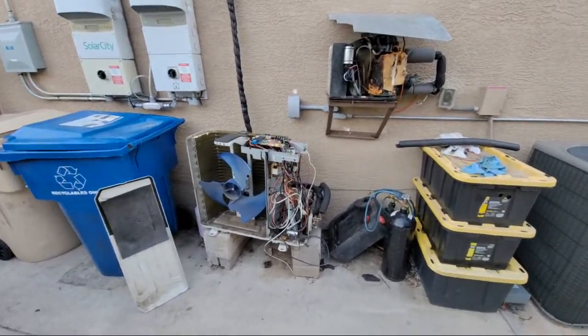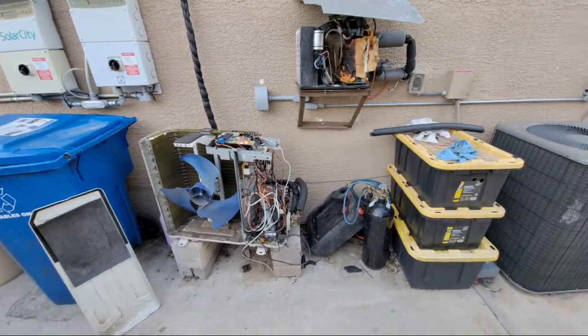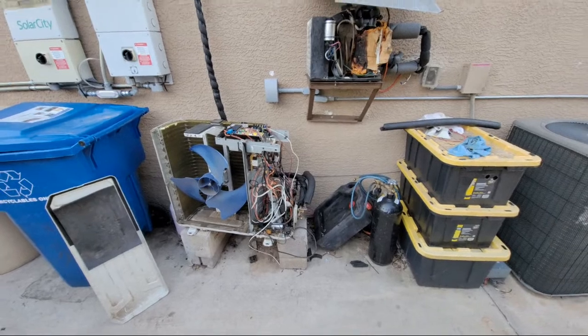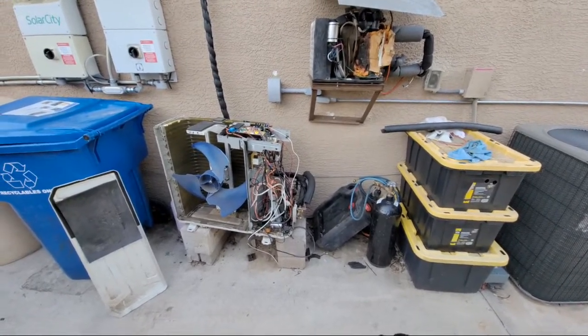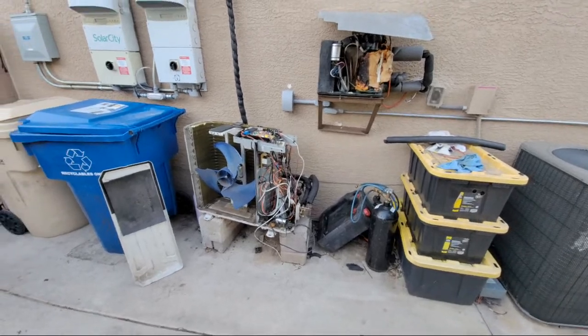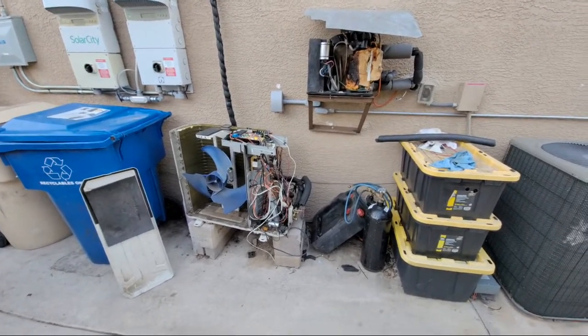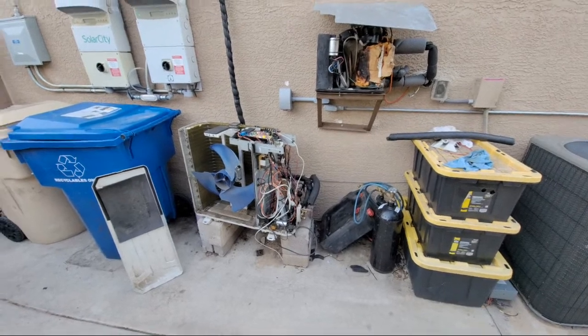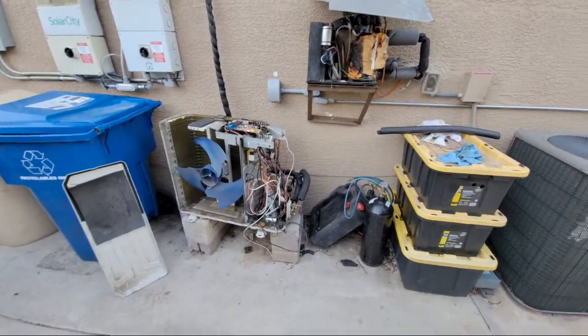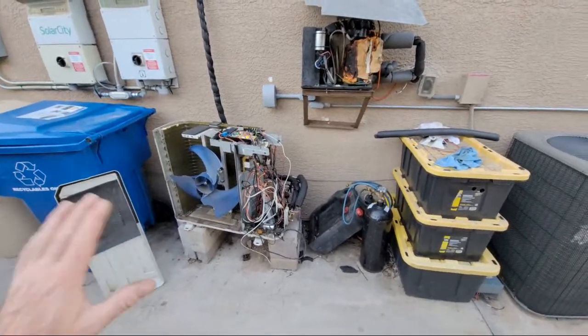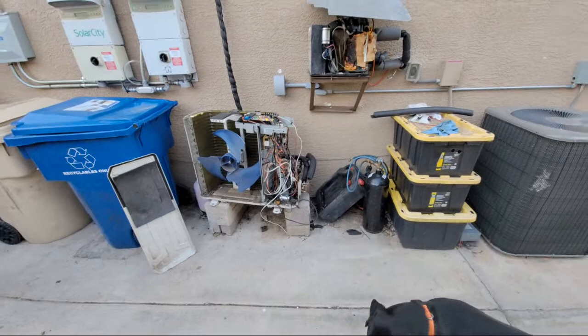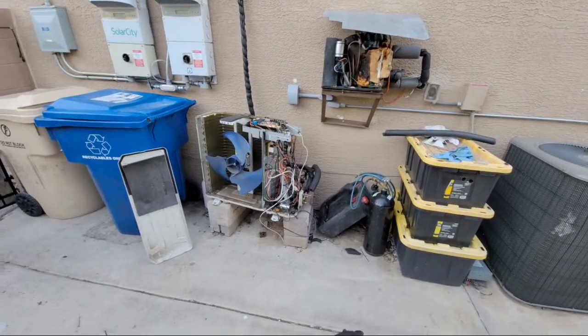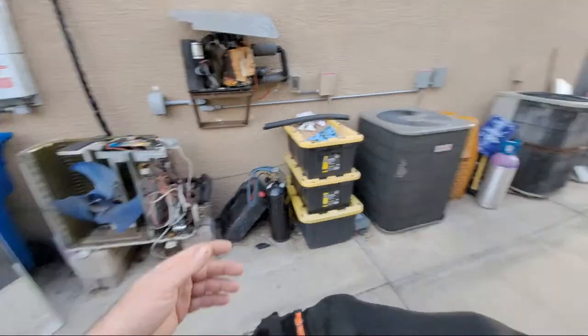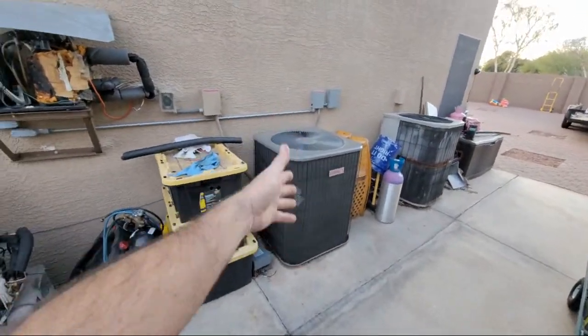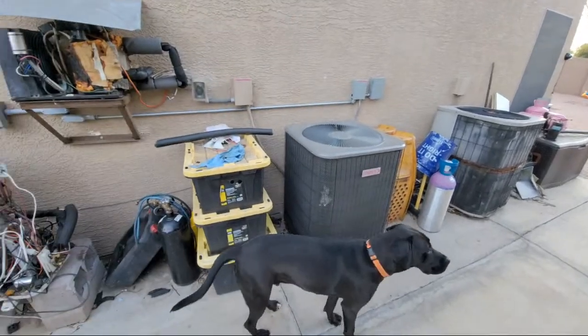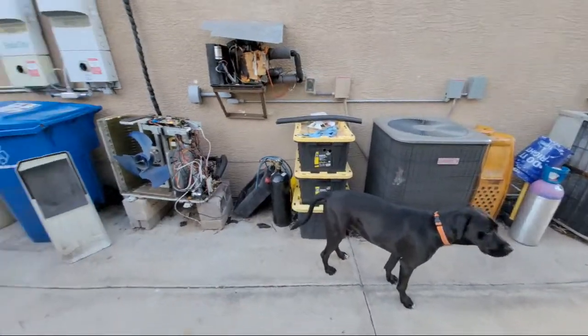Let me back up. During this last week I looked to see what my options were for compressors, and I thought it'd be nice to get a 3-phase scroll, since I have VFDs. The smallest one I can find is a 2-ton, and I'd only use that capacity when I needed to speed it up for heat—otherwise it'd be backed way down. With the smaller circuits, I don't think it would have any issue with oil return, because it's all about velocity. If you turn down a scroll that's matched for a circuit too much, the velocities in the pipes just don't bring back the oil.